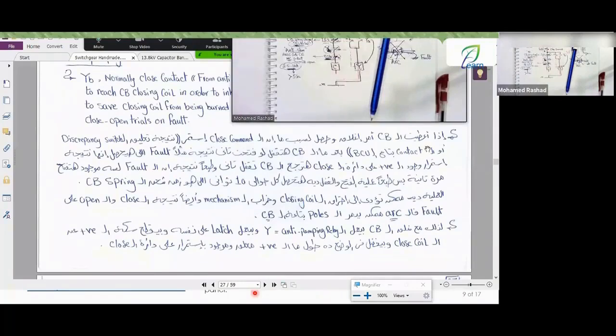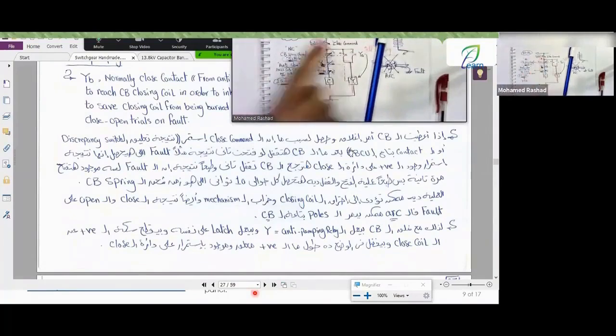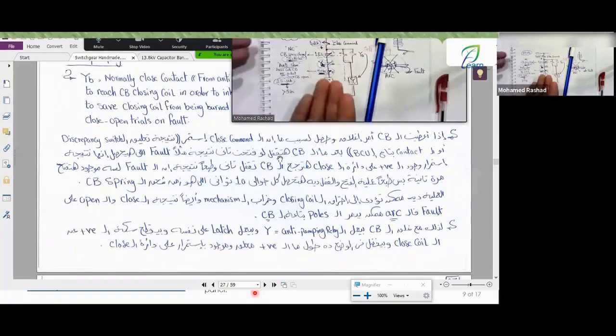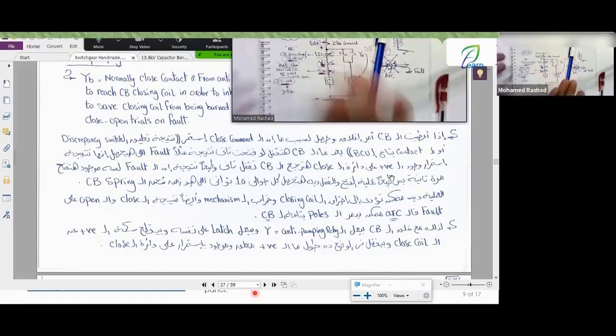I'm telling you, if you give the circuit breaker a close command, okay? And for some reason, this close command continues, meaning it remains stuck due to a discrepancy switch or a contact being stuck on the BCU. After the circuit breaker closes, if it opens again due to a fault, for example, what will happen is that due to the continued presence of the DC on the closing circuit, the circuit breaker will close again. And of course, since the fault itself hasn't been fixed, the voltage is still present, it will open again. But of course, this opening and closing process will happen approximately every 10 seconds, which is the charging time of the spring, which is specific to the closing operation.